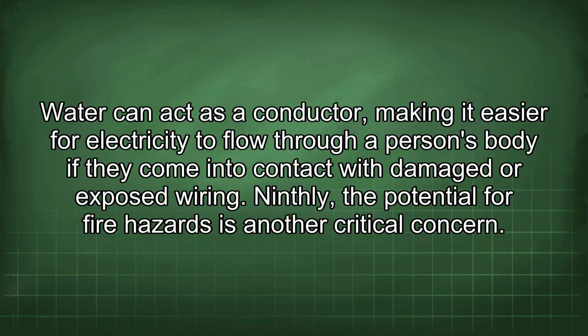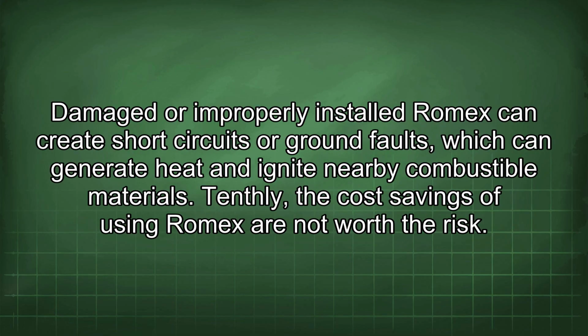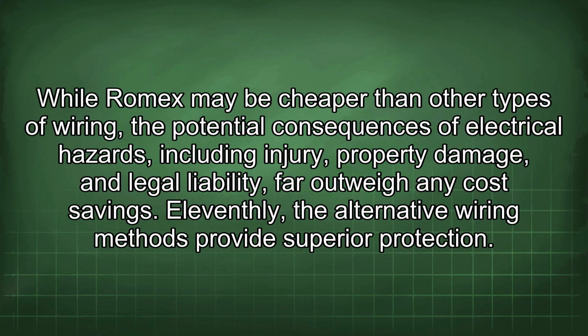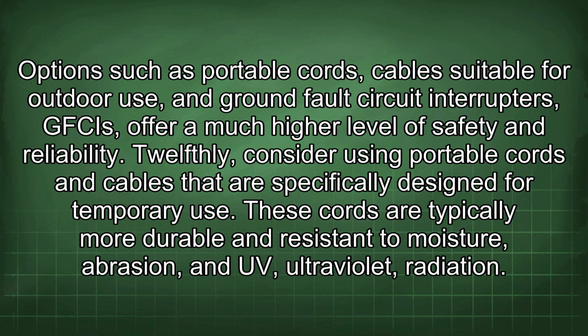Ninthly, the potential for fire hazards is another critical concern. Damaged or improperly installed Romex can create short circuits or ground faults, which can generate heat and ignite nearby combustible materials. Tenthly, the cost savings of using Romex are not worth the risk. While Romex may be cheaper than other types of wiring, the potential consequences of electrical hazards, including injury, property damage, and legal liability, far outweigh any cost savings. 11thly, the alternative wiring methods provide superior protection. Options such as portable cords, cables suitable for outdoor use, and ground fault circuit interrupters (GFCIs) offer a much higher level of safety and reliability.